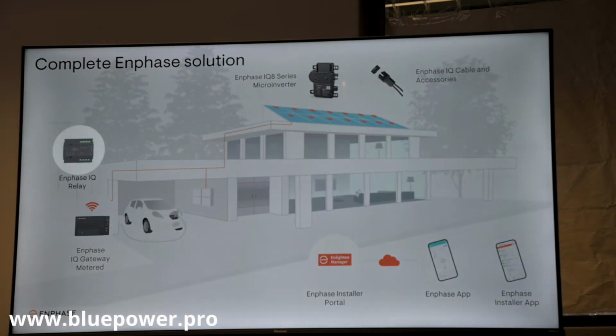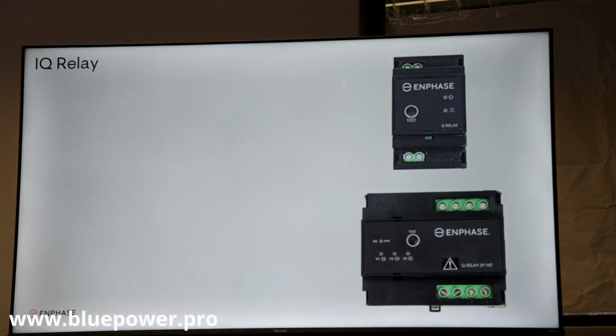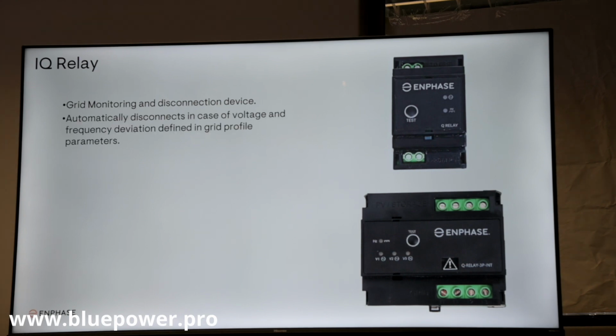Right, so now we're getting to the app. Okay, let's have a look at the relay. As I said, 2 relays - single phase and a 3-phase relay. These are for monitoring, it's a monitoring device and also a disconnect device. So when that relay senses there's a problem with the grid voltage - a drop in grid voltage, or the frequency is incorrect - that unit will automatically disconnect the microinverters from the grid, which is a nice function.